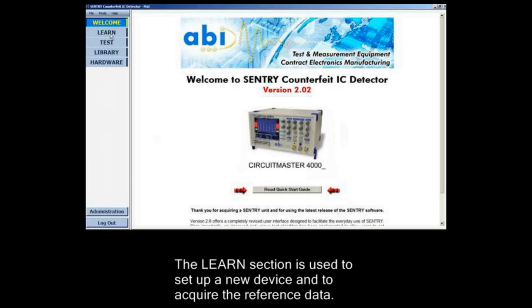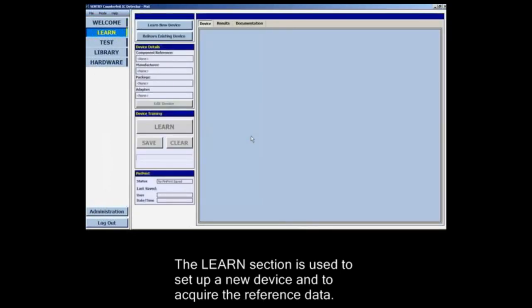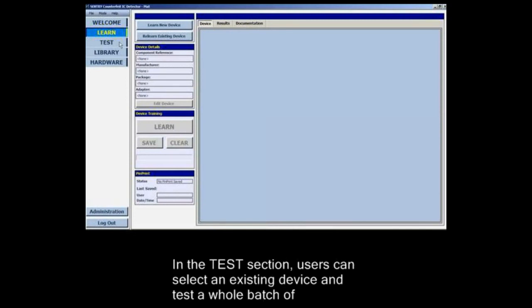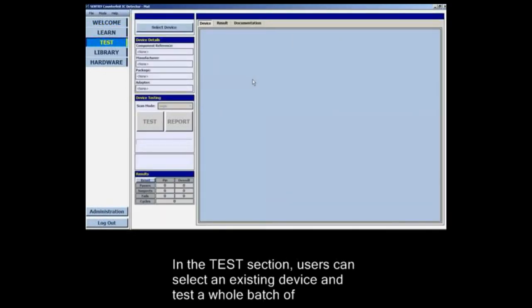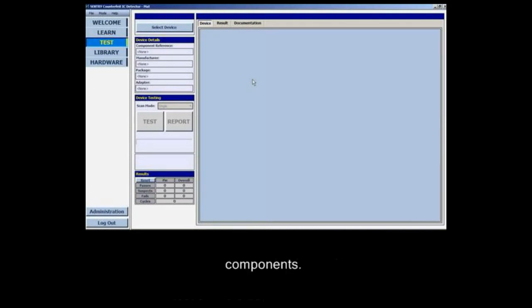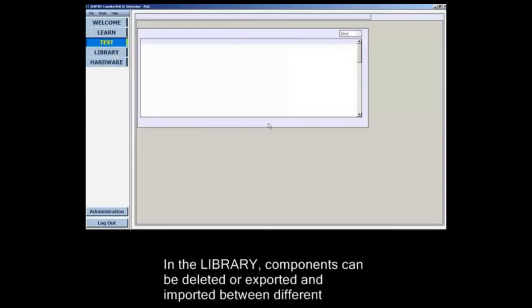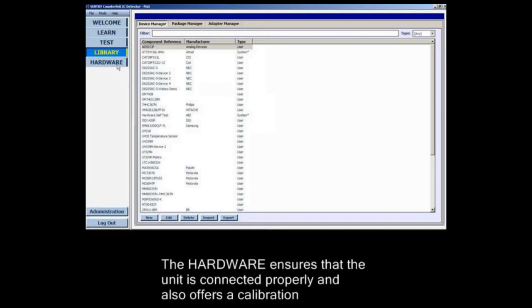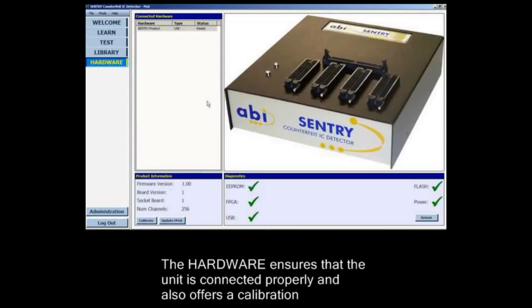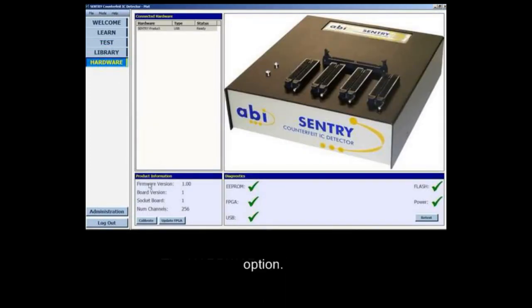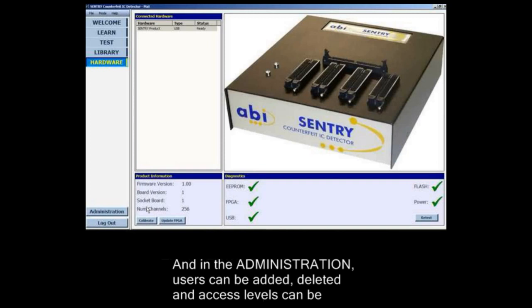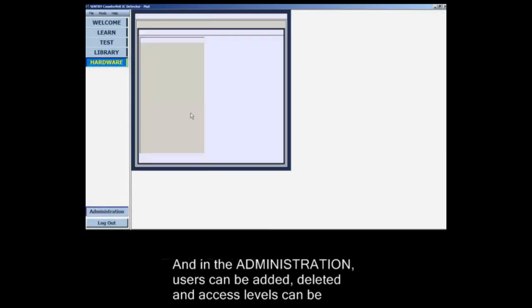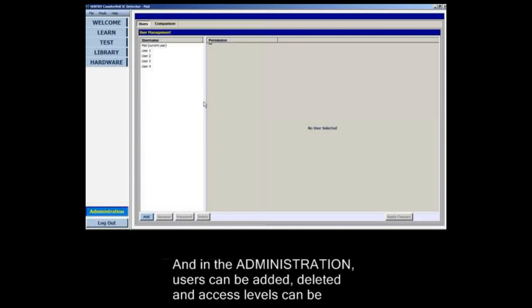The learn section is used to set up a new device and to acquire the reference data. In the test section users can select an existing device and test a whole batch of components. In the library, components can be deleted or exported and imported between different machines. The hardware section ensures that the unit is connected properly and also offers a calibration option. In the administration section, users can be added, deleted and access levels can be granted.